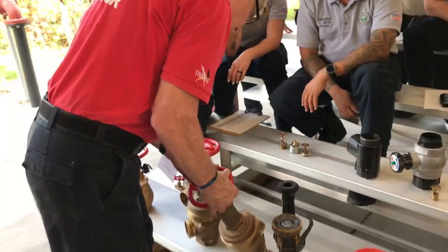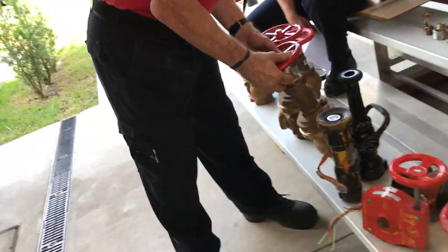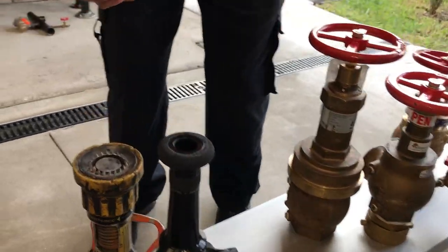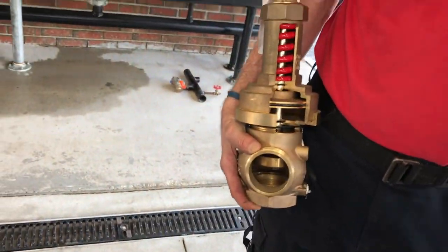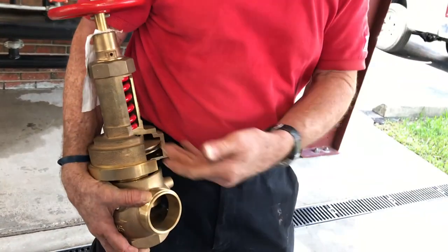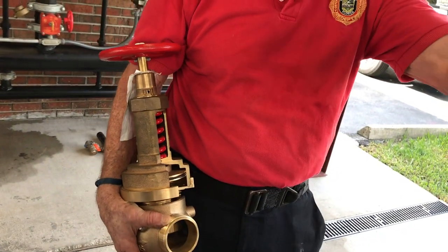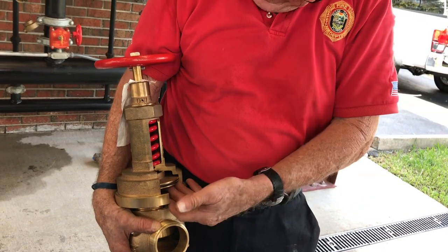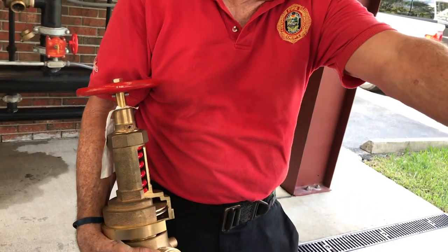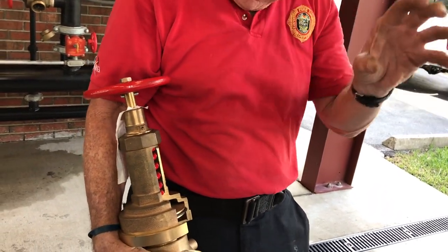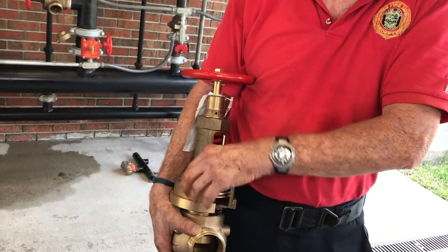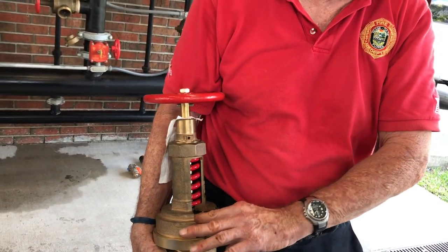Valve, you can see the spring. Spring, the amount of tension. This works exactly the opposite as our relief valve. Whereas the tension of the relief valve would work against the relief valve to keep it closed, tensioning this will have a tendency to open the valve, and work against the water that's acting upon the piston here.